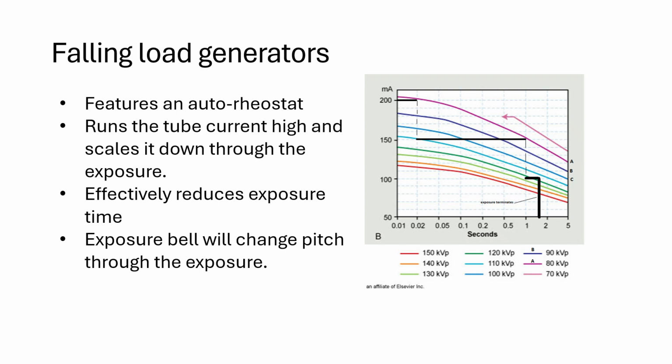We deliver the appropriate quantity of mAs. Okay. I think if you multiply those up, it was either like 145 mAs or 198 mAs, something like that. But that's the shortest exposure time possible on this unit. Okay.